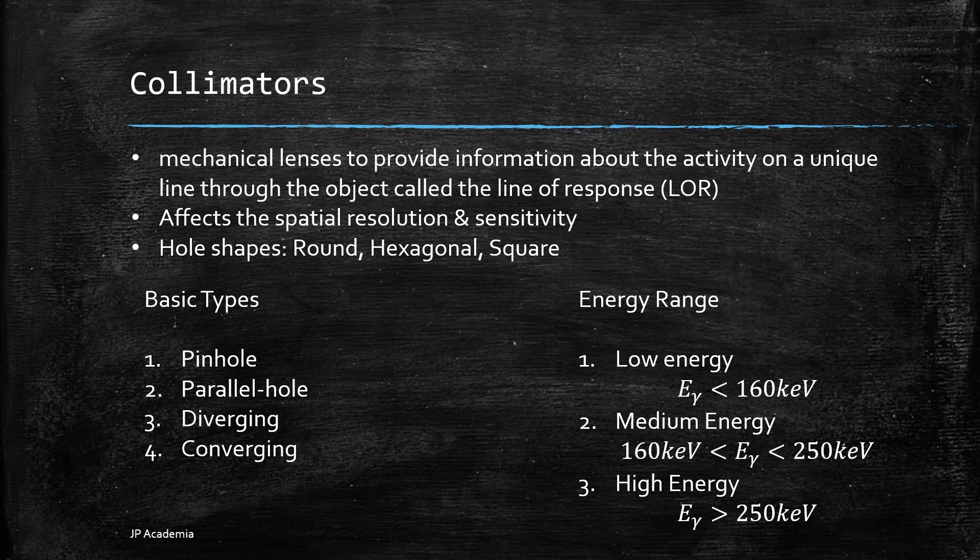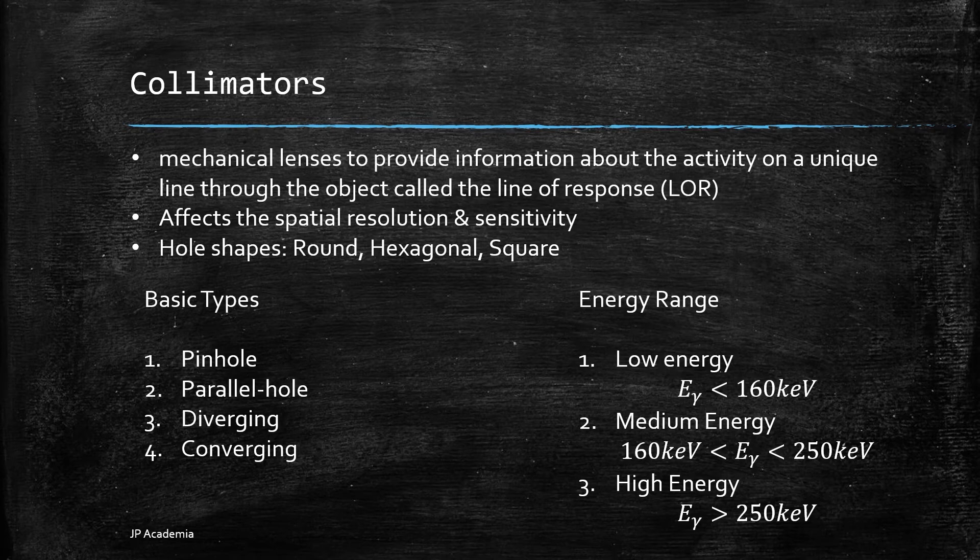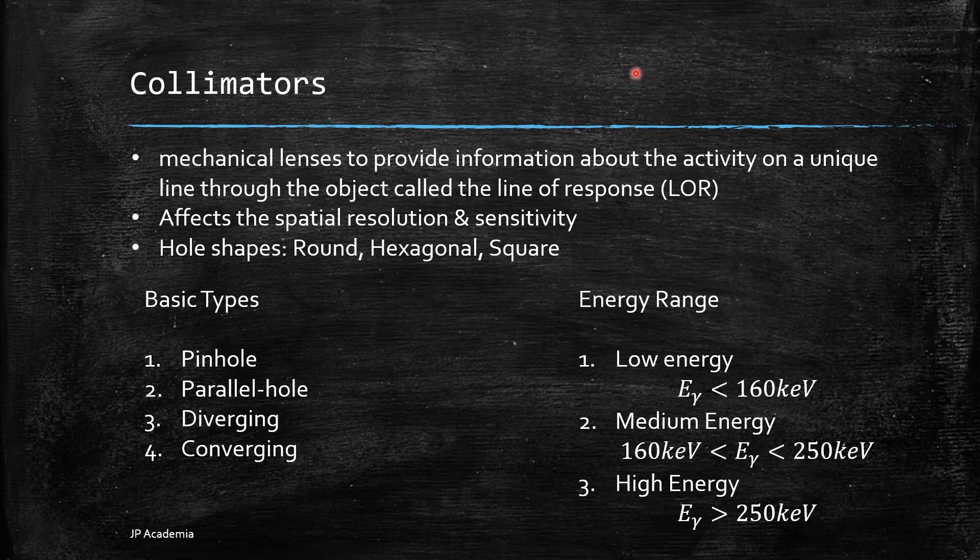Collimators are used as mechanical lenses to provide information about the activity on a unique line through the object called the line of response or LOR. The collimator prevents photons emitted along directions that do not lie along the line of response from reaching the detector. We usually use hexagonal holes in continuous crystals camera. The basic types of collimators according to the hole geometry are the following.